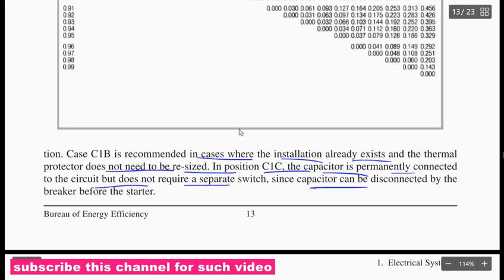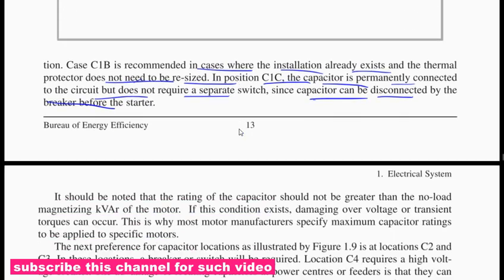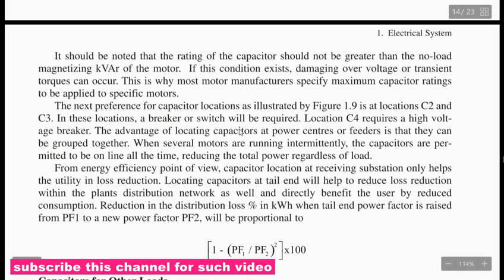The capacitor is controlled by the breaker before the starter. It should be noted that the rating of the capacitor should not be greater than the no-load magnetizing kVAr of the motor, otherwise damaging overvoltage and transient torque can occur. This is why motor manufacturers specify the maximum capacitor rating to be supplied with a specific motor.